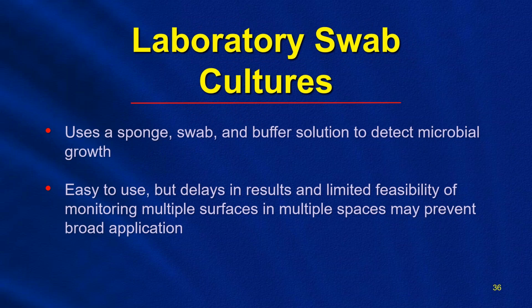So using laboratory cultures to check for residual bioburden or cleanliness, although it's an easy test and will provide specific data about which pathogens may be growing, it has its time constraints. It's not a quick and efficient test, as we can be waiting for several days for results to come back. So if you want to test your surgical instruments after the cleaning process before sterilization and you send out a culture, do you have 2 days to wait to start sterilizing those instruments to see if they've been cleaned effectively?